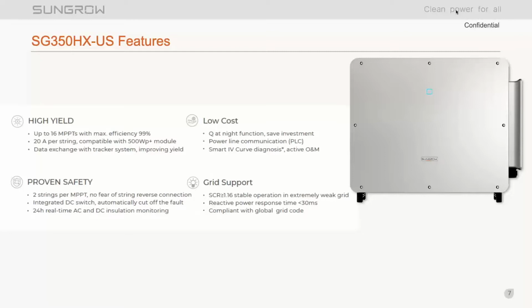Safety is another consideration. We're always looking at ways to improve the safety and the reliability of the inverters. So with our direct input design, we're still maintaining the architecture of having only 2 strings per power point tracker. So you really don't need to worry about reverse connections and overcurrent devices that you would need in systems that have more than 2 strings per power point tracker.